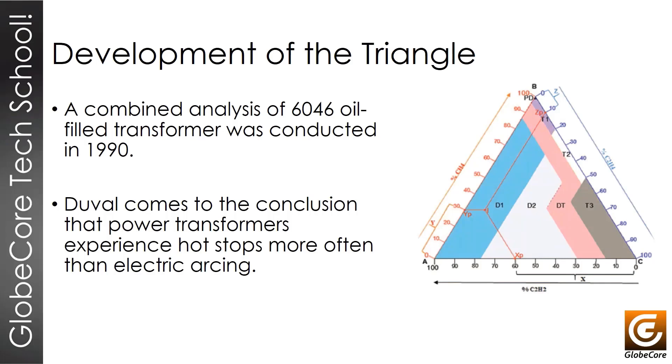The method was first presented in 1974, and although at that time it was not perceived as a triangle, Duval demonstrated three specific features. Duval concluded that hydrogen dissipates on metal and other points of the transformer, so he decided to use three hydrocarbon components, specifically methane, ethylene, and acetylene, and thus he developed his triangle.